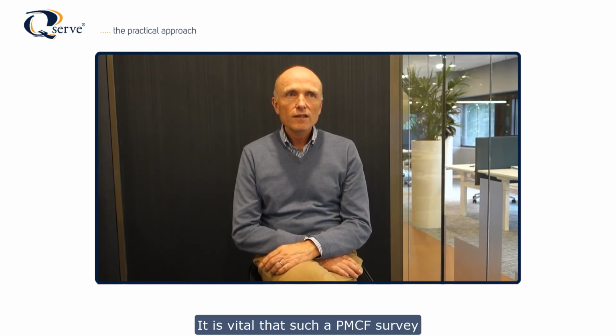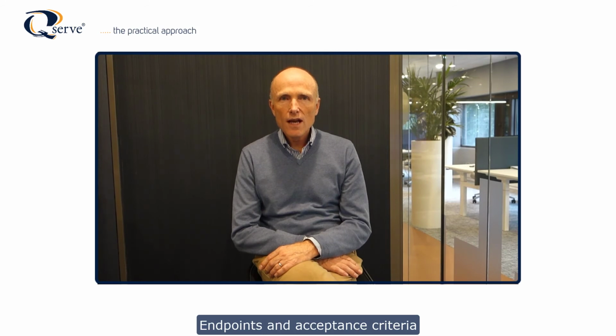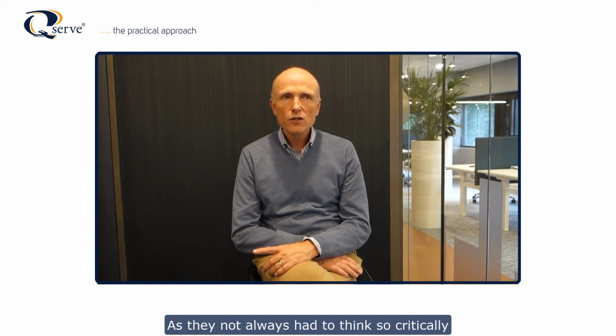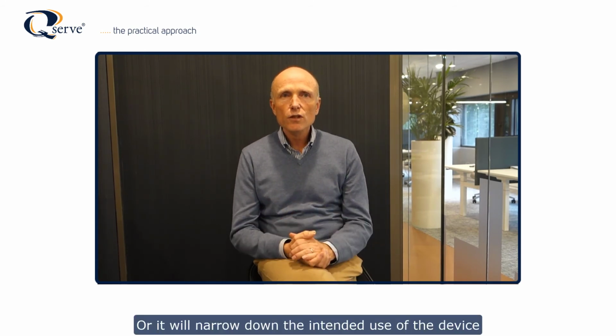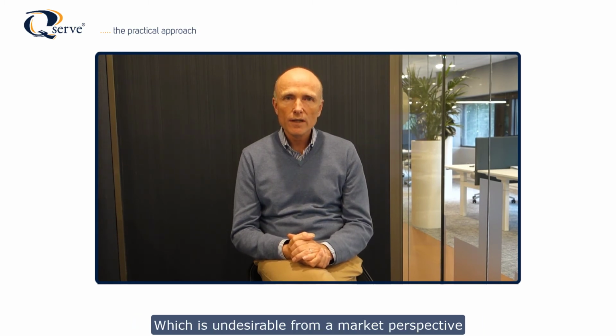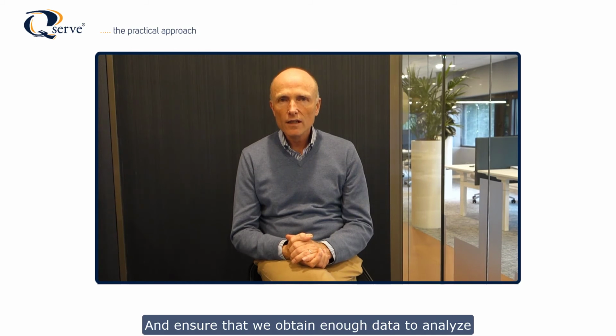It is vital that such a PMCF survey is conducted in a controlled manner, following the principles of good clinical practice or ISO 14155. The first step is to define carefully the clinical safety and performance endpoints and acceptance criteria. We see in practice that our clients often struggle with this, as they not always had to think so critically about these aspects, or it will narrow down the intended use of the device, which is undesirable from a market perspective. After that, the statistics come into play to define the number of surveys to be sent out and ensure that we obtain enough data to analyze.